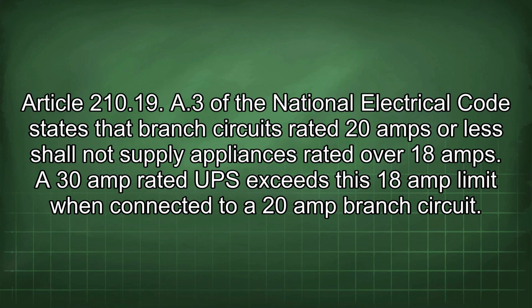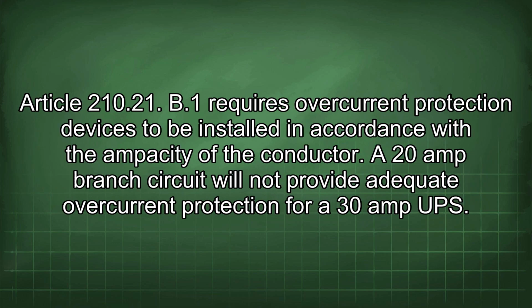Article 210.19(A)(3) of the National Electrical Code states that branch circuits rated 20 amps or less shall not supply appliances rated over 18 amps. A 30 amp rated UPS exceeds the 18 amp limit when connected to a 20 amp branch circuit. Article 210.21(B)(1) requires overcurrent protection devices to be installed in accordance with the ampacity of the conductor. A 20 amp branch circuit will not provide adequate overcurrent protection for a 30 amp UPS.